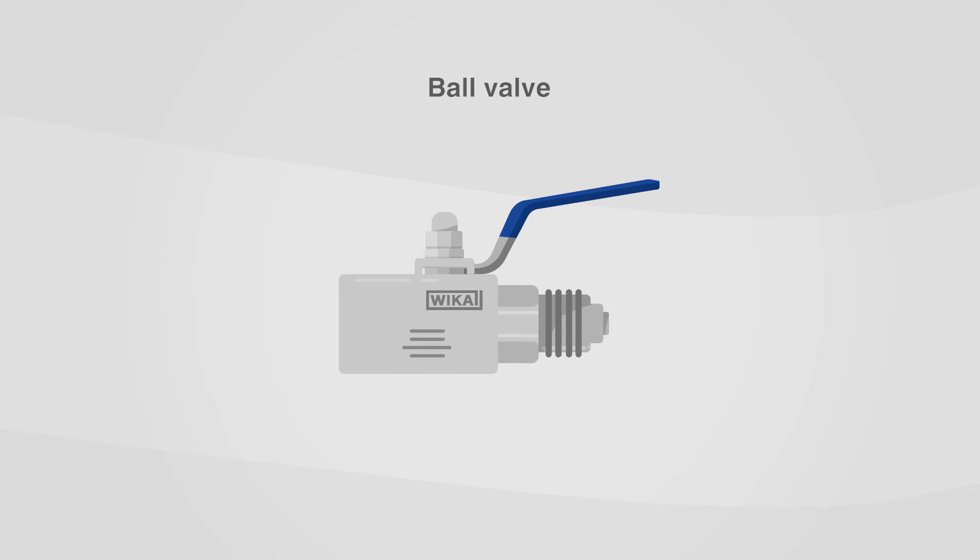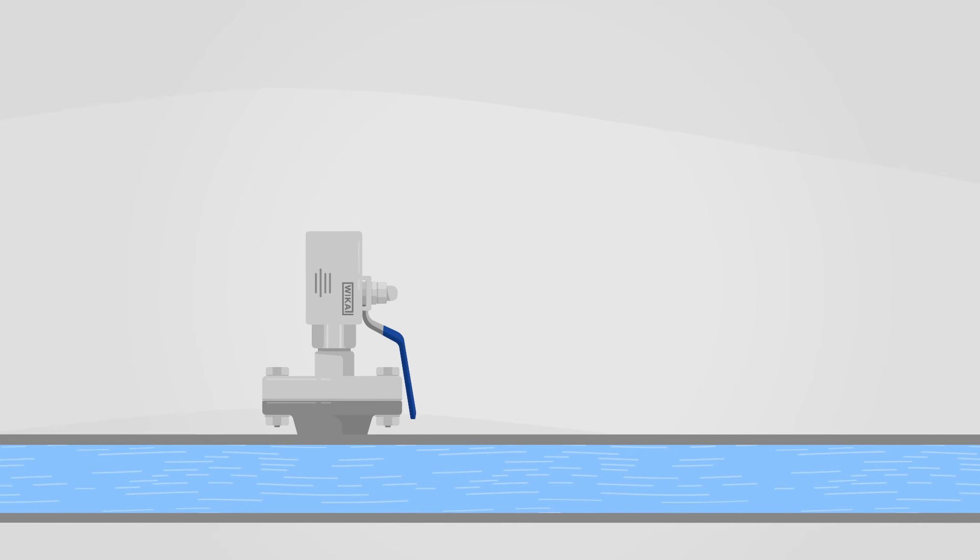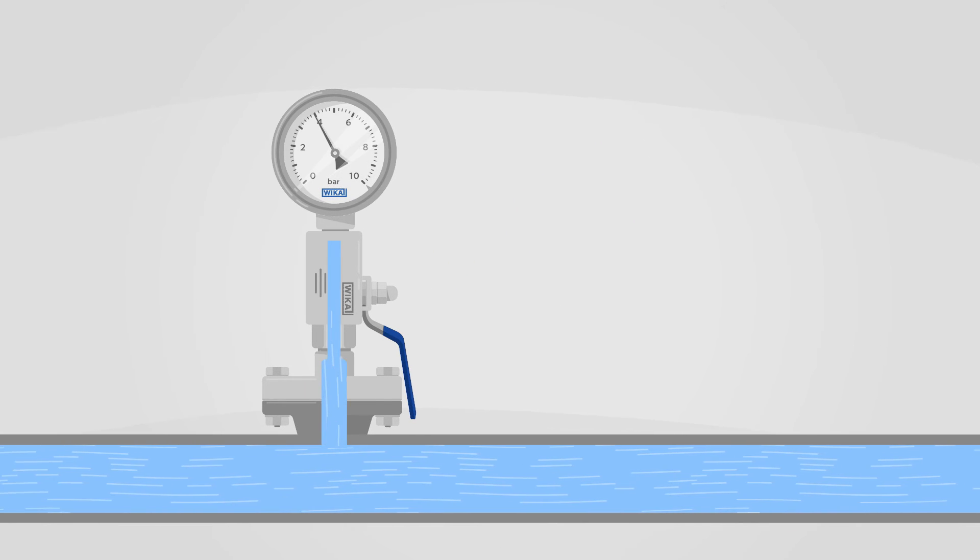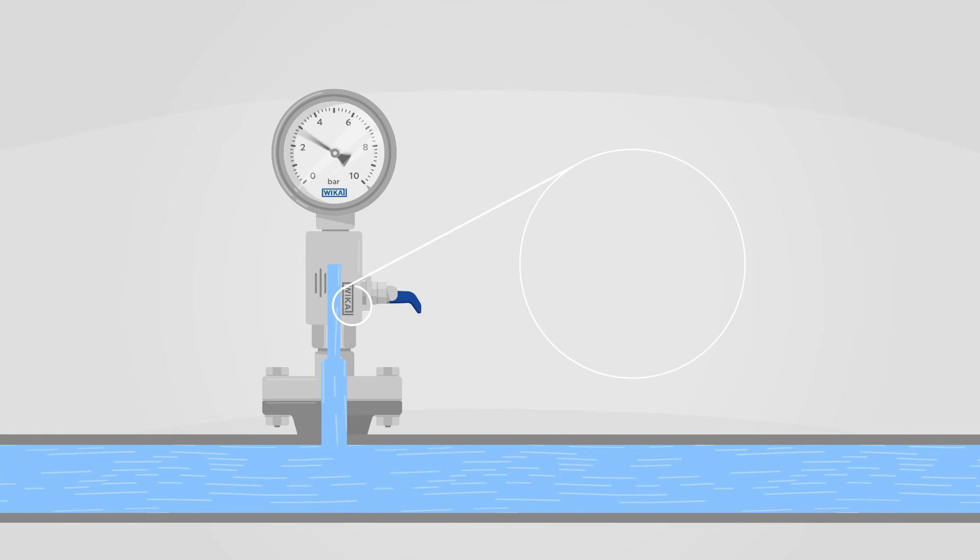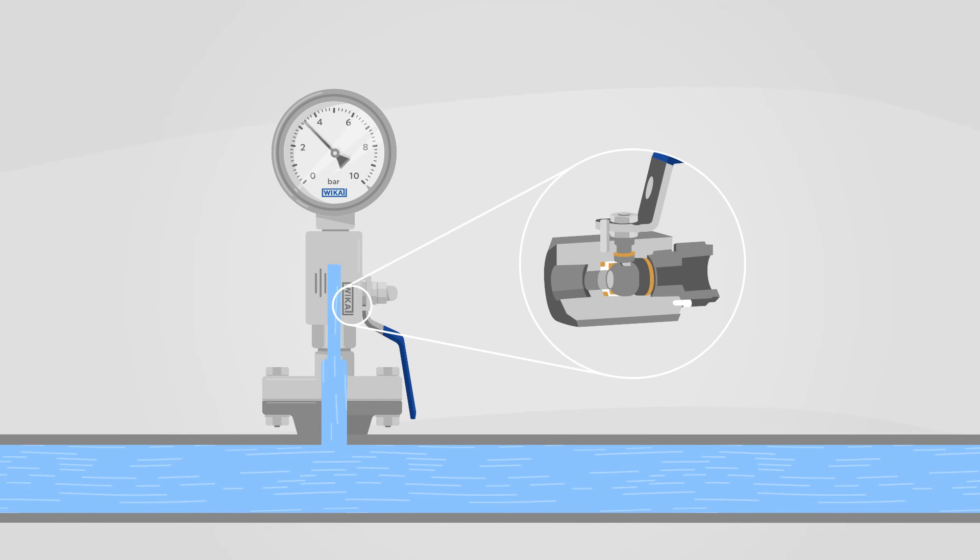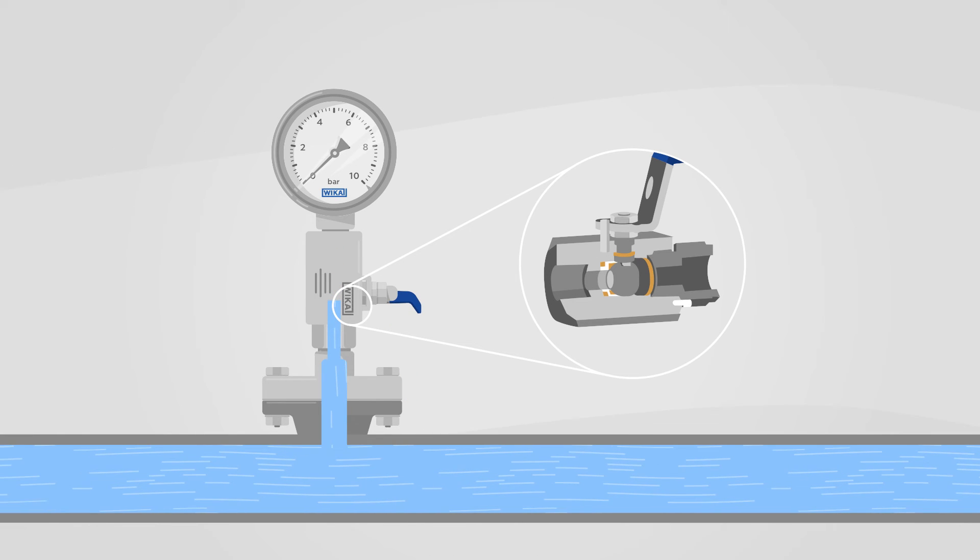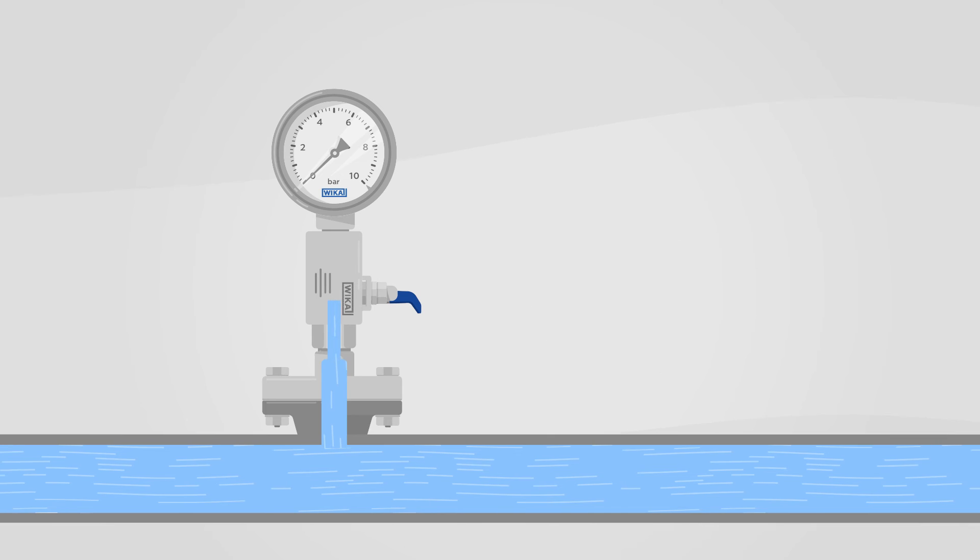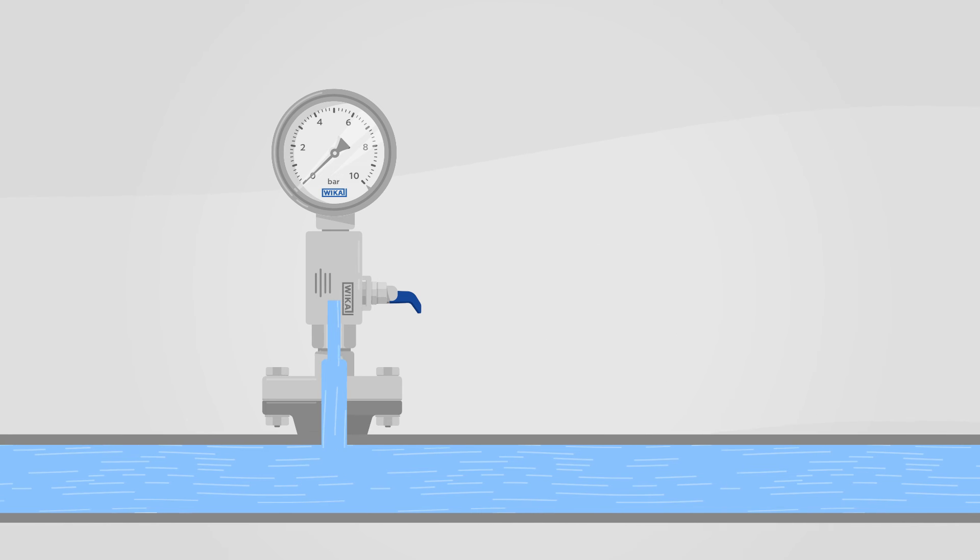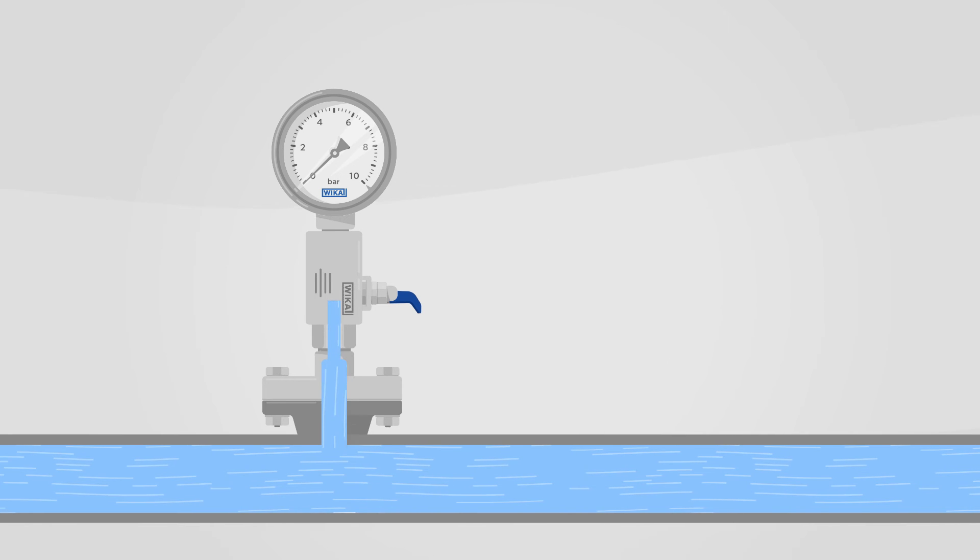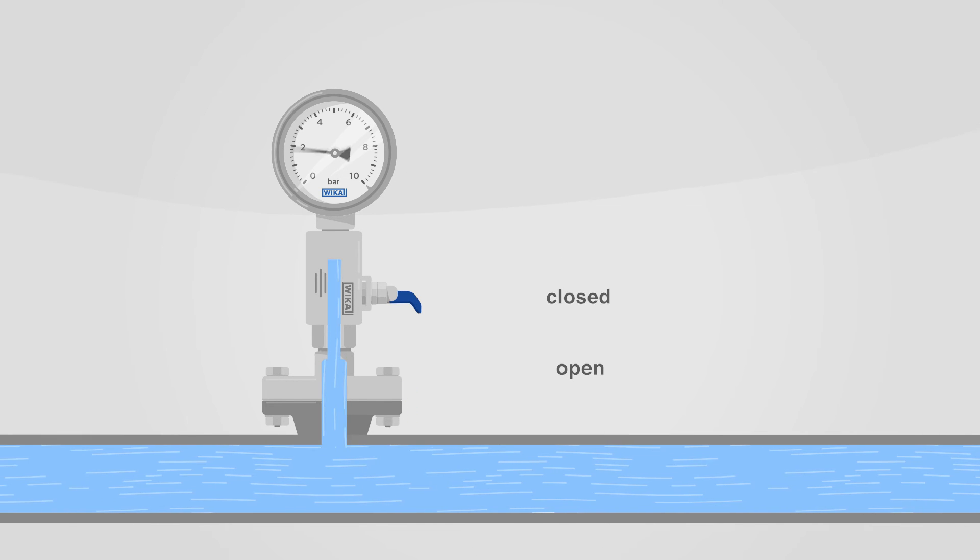Ball valves have a different closing mechanism and are often used in applications with large pipe diameters. They close the process quickly and reliably using a ball. To open or close, the handle is turned through 90 degrees, making it possible at a glance to see whether the ball valve is open or closed.